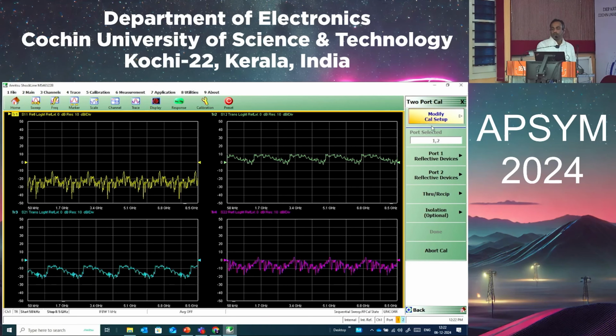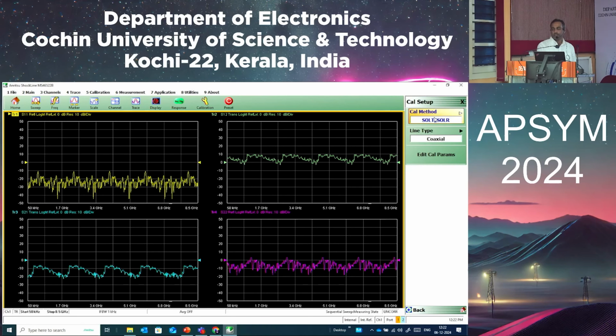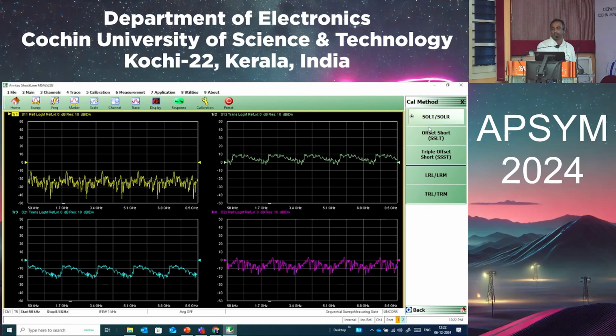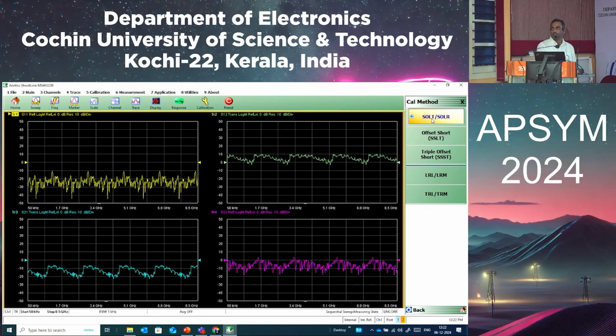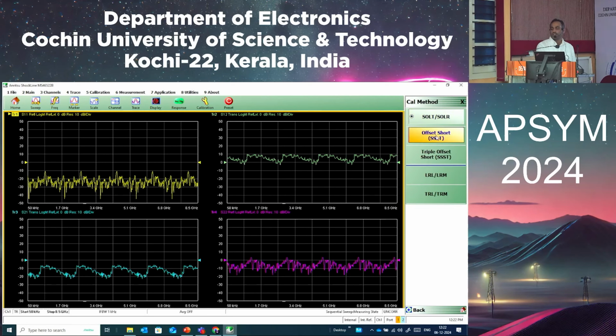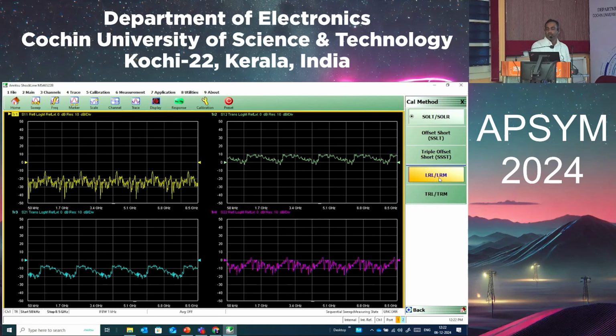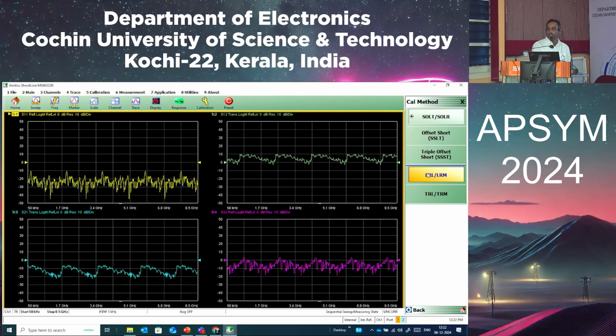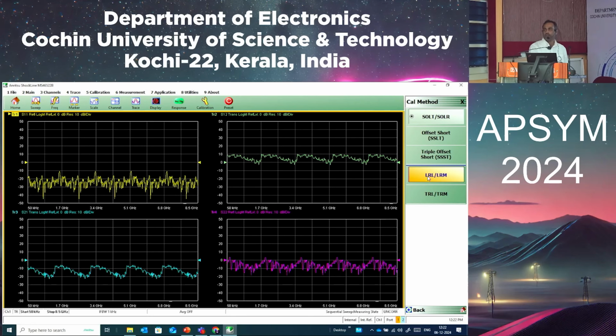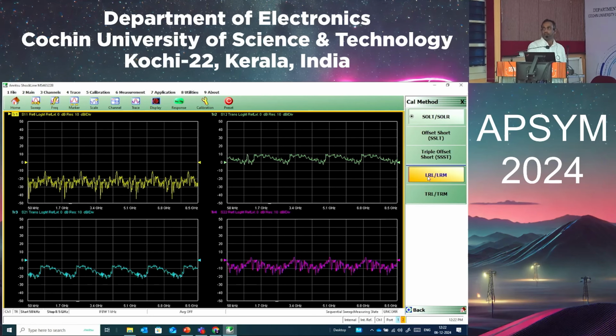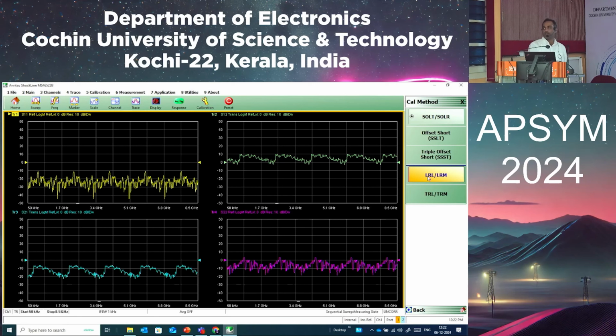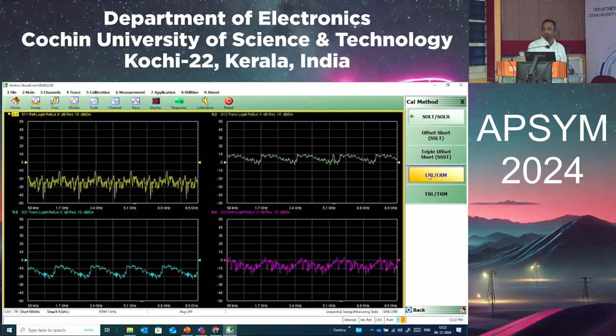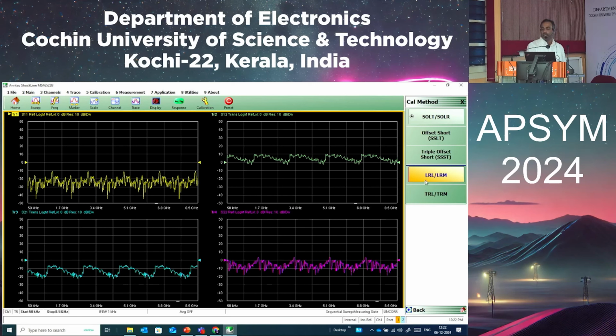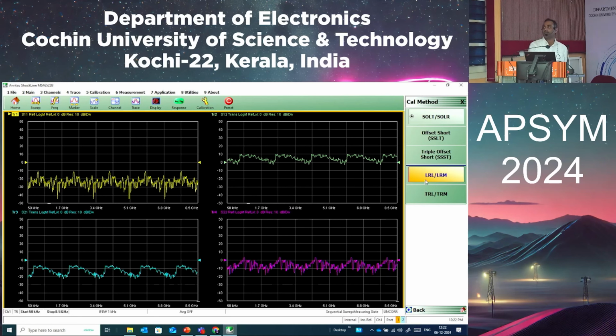Okay, so once we have done that, you can go to modify cal setup. In this you can select SOLT, SSLR, SSLT. SSLT and SSST are used for waveguide calibration. Okay, and for LRL and TRL, this has to be known. LRL means line reflection line. You have to know the electrical length of the line or reflection. It may be an open or a short. You have to know these values, the electrical length of this, and we can enter those values and we can do the calibrations.